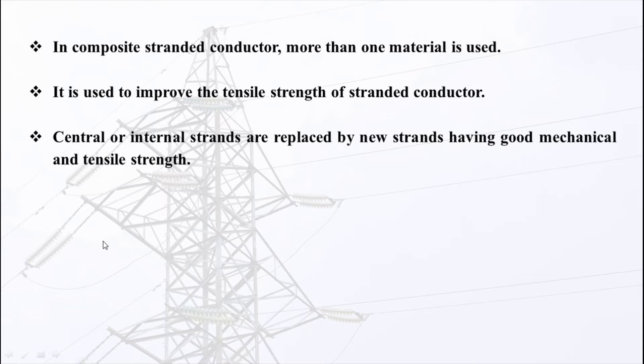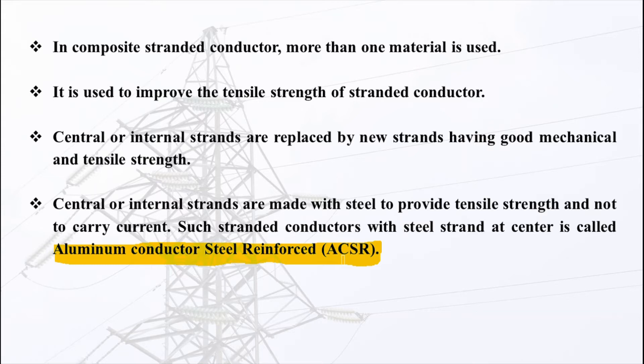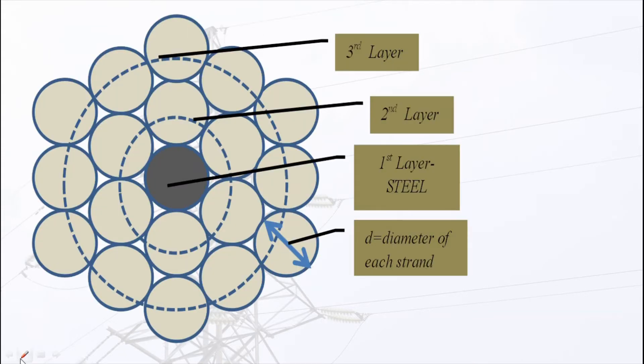For example, ACSR is a composite stranded conductor. ACSR stands for Aluminum Conductor Steel Reinforced. In an ACSR conductor, the central or internal strands are made up of steel, which has very good tensile and mechanical strength. In this way the overall tensile strength of the conductor is improved, because steel is used at the center. The steel conductor is used to provide tensile strength only and does not carry any current.